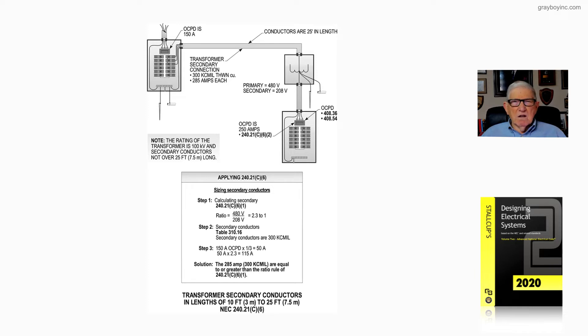You know, there was always a conflict between 240.21C3 because it said industrial. So a lot of cities, states, and counties said, well, you have to be in industrial-type zoning to make this 25-foot tap. You have to make a 10. So we needed to do something for commercial areas where a tap rule could be made over 10 foot up to 25. So the code panel came up with 240.21C6.